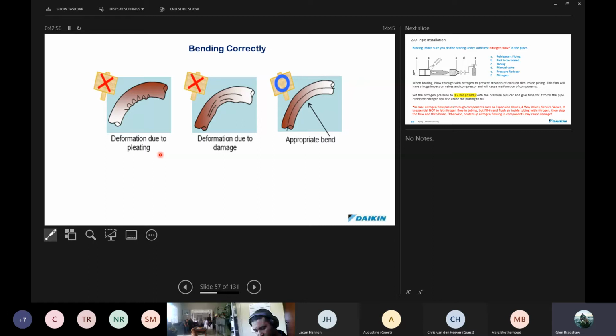So what are we looking for when we bend pipes? Well, one, like I said, we want a uniform bend. So we don't want to see any pleating or ribs around the inside of the piping that you would get if you bent it over your knees. We don't want to see any deformation or damage to the piping. In other words, when we talk about uniform, we want to see a diameter that remains the same throughout the bend, from the time it enters to the time that it leaves. We don't want to see the pipe kinked in any way or deformed from a round to an oval shape. It must be constant in shape all the way through the bend. So that's the type of thing that we're looking for.